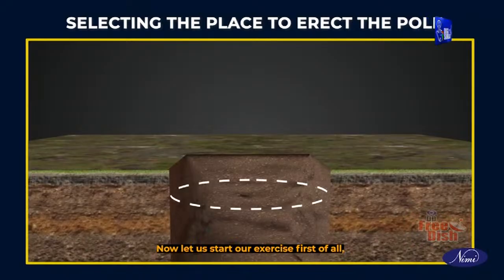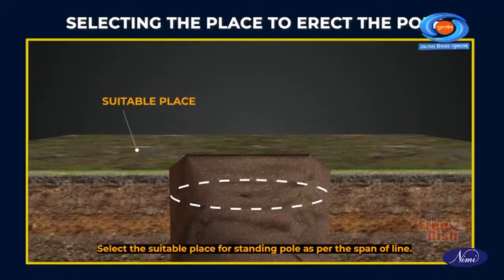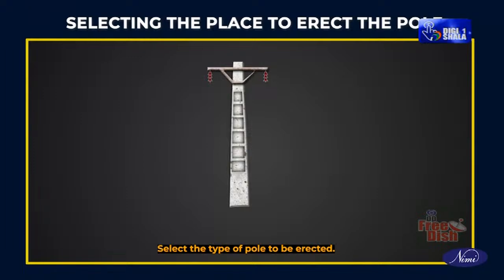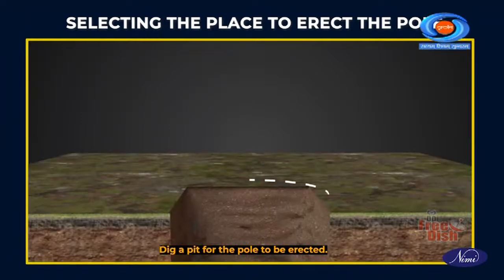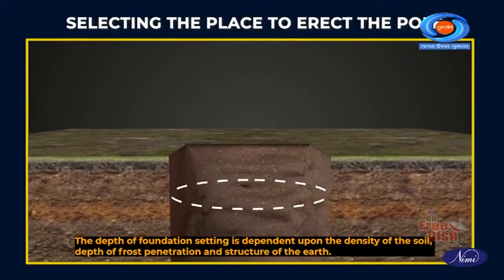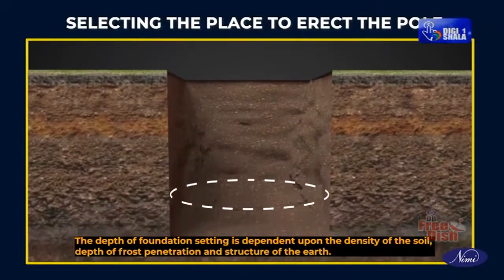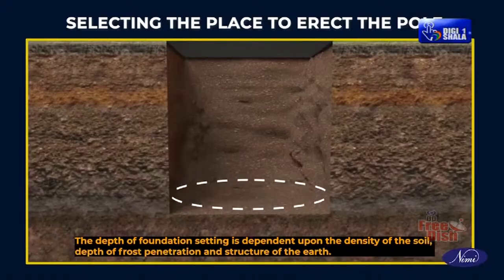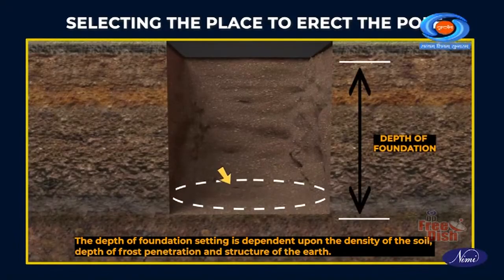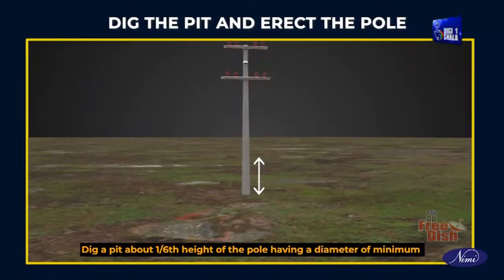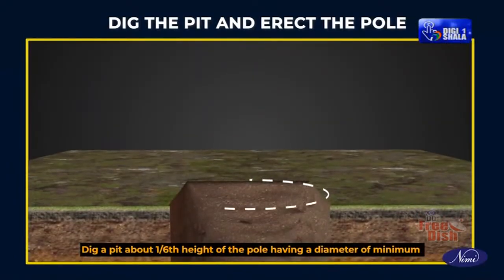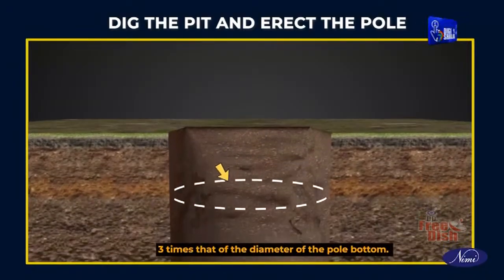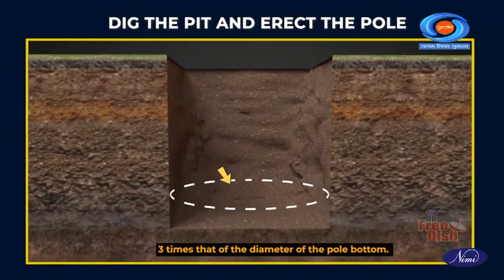Now let us start our exercise. First of all, select the suitable place for standing pole as per the span of line. Select the type of pole to be erected. Dig a pit for the pole to be erected. The depth of the foundation setting is dependent upon the density of the soil, depth of frost penetration and structure of the earth. Dig a pit about 1/6 height of the pole having a diameter of minimum 3 times that of the diameter of the pole bottom.